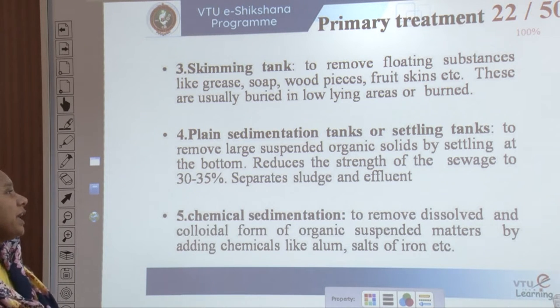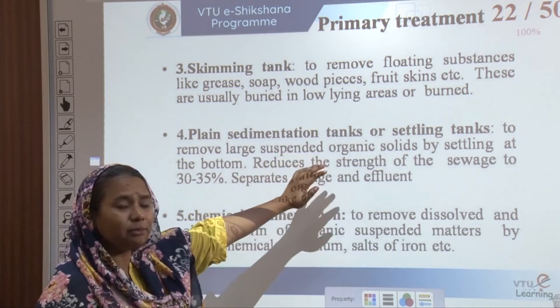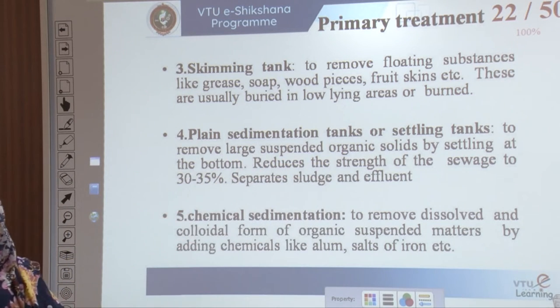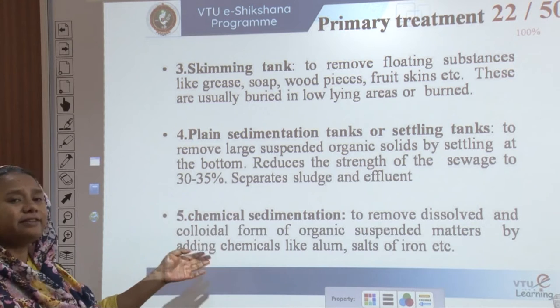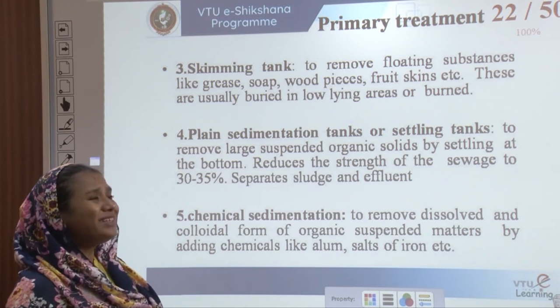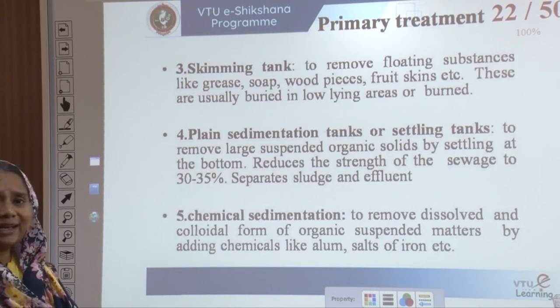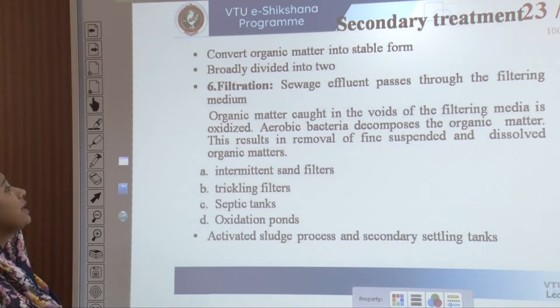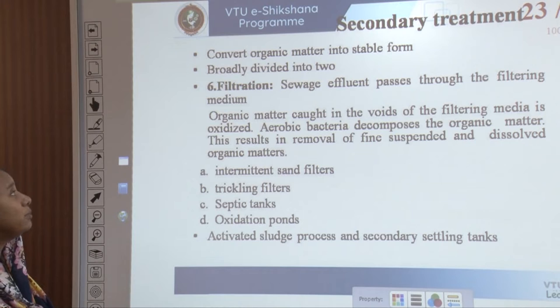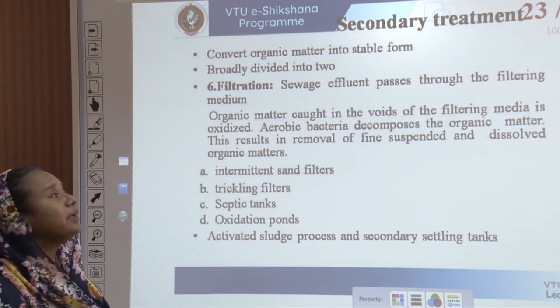Plain sedimentation tanks or settling tanks remove large suspended organic solids by settling at the bottom. The strength of the sewage is reduced by 30 to 35 percent by the time it enters the sedimentation tanks, which separate sludge and effluent waste. After separation it enters the chemical sedimentation area, where dissolved and colloidal organic suspended materials are segregated by adding chemicals like alum and salts of iron. After this, conversion of organic matter into stable form takes place, leading into the secondary treatment.